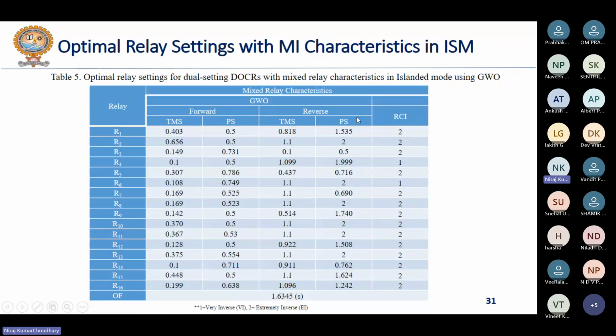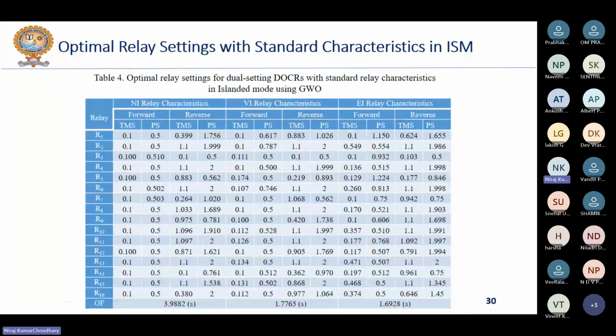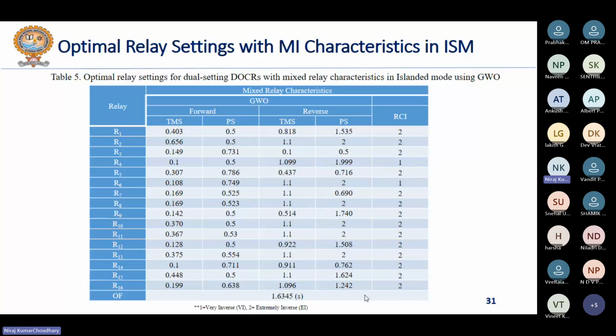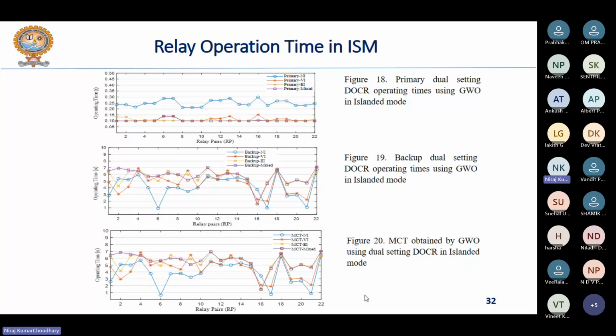And similarly, with mixed inverse characteristics, we have optimally determined the relay characteristic curve using RCI as a decision variable, and we are getting the total time of operation of the relays, that is the value of the objective function, as 1.6345 second. Again, less than the total time of operation in case of NI, VI, and EI characteristics. What does it mean? It means that the mixed inverse characteristics of relays are providing a better result in terms of the total time of operation of the relays. What does it mean? It means that if you use the mixed inverse characteristics, then the fault will be cleared in less time, right? And similarly, the time of operation of the primary and backup relays and the measured coordination time interval are obtained as shown in the three figures.